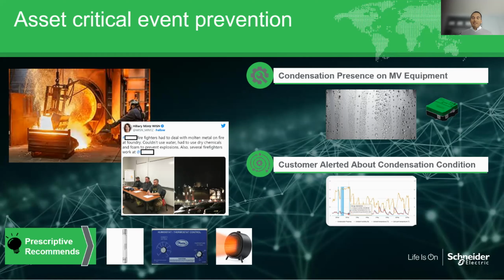Now, number two: is the thermostat set to the correct settings so that the heater in this piece of equipment properly turns on, to lower the humidity levels so condensation doesn't happen, or maybe it's too hot and that's why condensation is happening? So is it on the right settings? Well, it looks like it is — the right settings for both temperature and humidity, because this thermostat controls both, turning on the heater in the presence of high humidity or low temperature. So okay, it is turning on correctly.